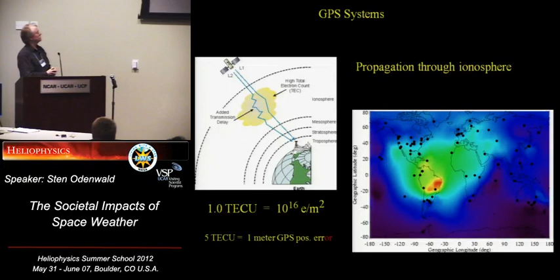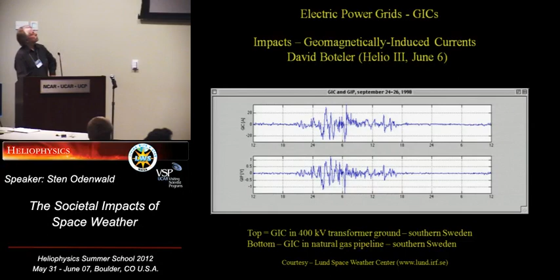Electric power grids—lots of good discussions about that, including one coming up by David. We see the effects of geomagnetically induced currents in a lot of different electrical and pipeline systems, so it's not a theory any longer, it's real world. Transformers can be seriously damaged by having GICs enter the circuitry, the primary windings. Temperatures over 200 centigrade or more have been reported in some of these transformers that are GIC active, and that leads to problems with insulation, punch-through, and a variety of effects that ultimately damage the transformer.